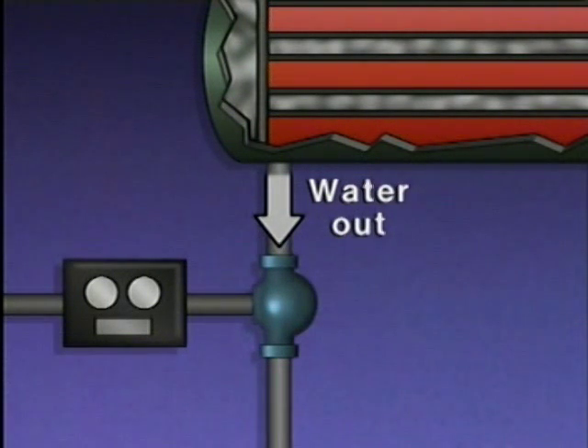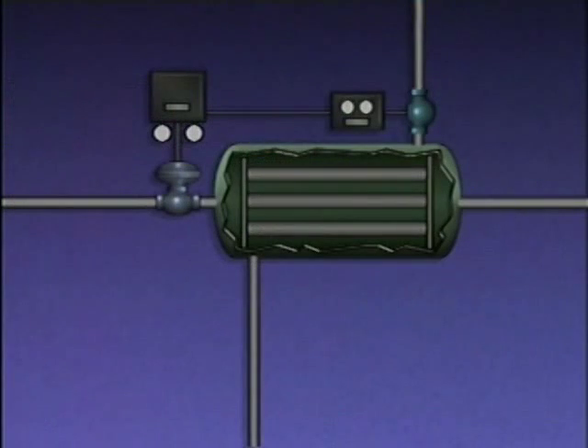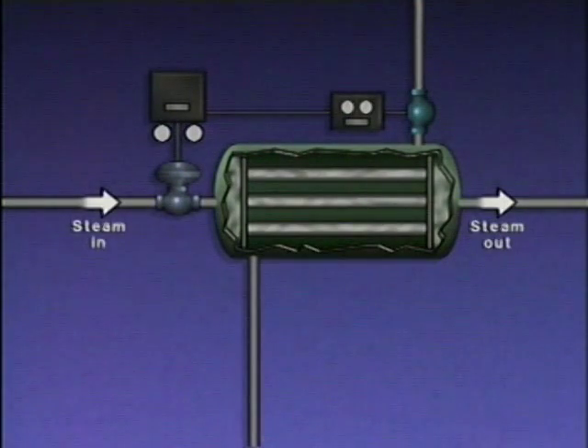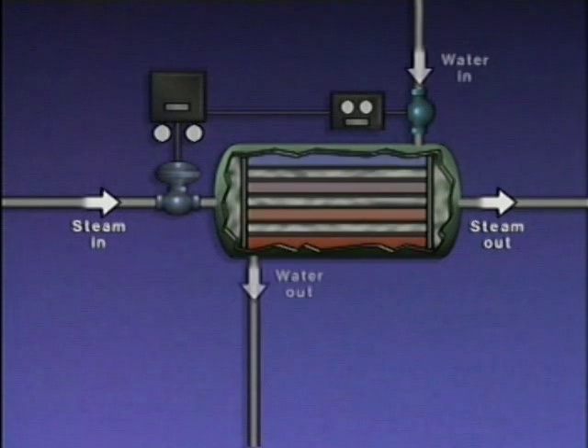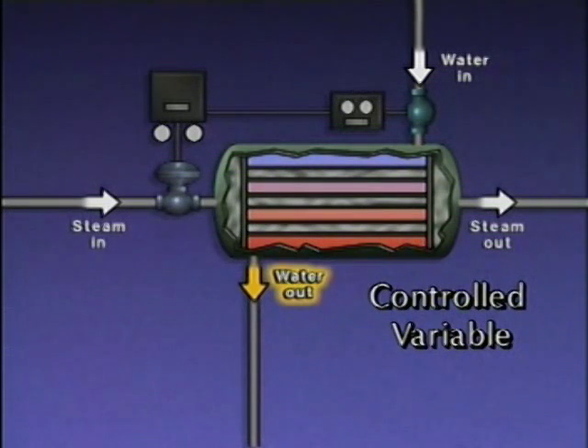A feedforward control system attempts to correct for a process disturbance before the controlled variable in the process deviates from set point. To get a better understanding of how a feedforward control system works, let's look at an illustration of a heat exchange process that's controlled by a feedforward system. In this system, steam flows through tubes inside a heater and heats water that flows around the tubes. The controlled variable in the system is the water temperature at the outlet of the heater.